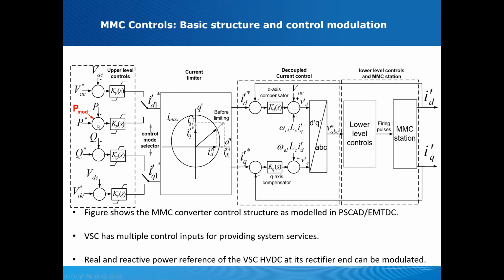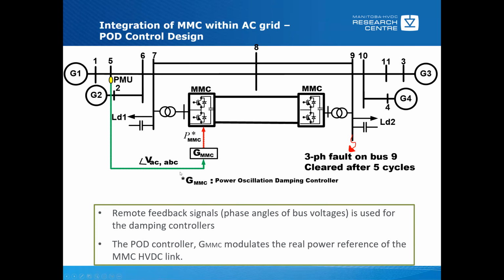So one option could be to modulate. For an MMC, for example, you have the ability to modulate active and reactive power independently of each other at both sides of the converter. Sorry, on one side PQ and on the other VDCQ. So you have three control freedoms, P, Q, and Q. In this example, I'm illustrating a very simple case where I'm going to modulate the active power of an HVDC link in order for the system oscillations to damp.